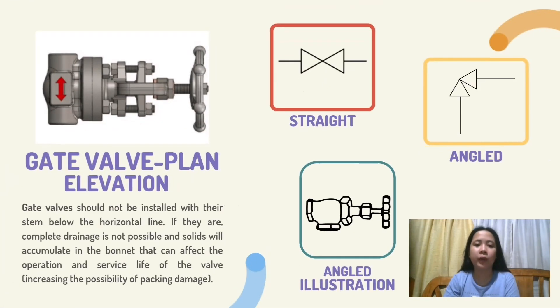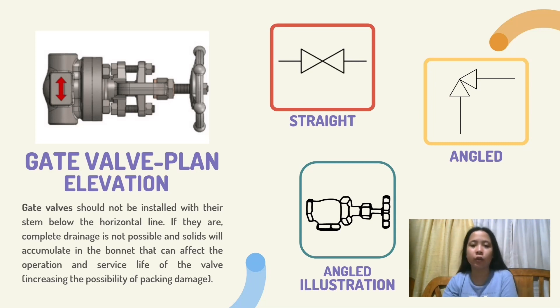Gate valves should not be installed with their stem below the horizontal line. If they are, complete drainage is not possible and solids will accumulate in the bonnet, which can affect the operation and service life of the valve, increasing the possibility of packing damage. Here is the symbol of gate valve elevation: straight, angled, and the angled illustration of gate valve elevation.